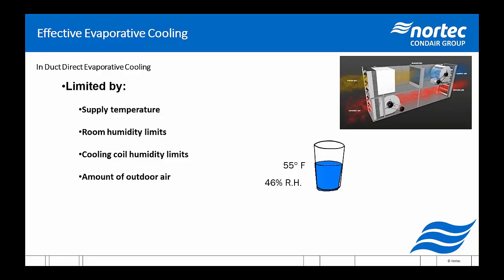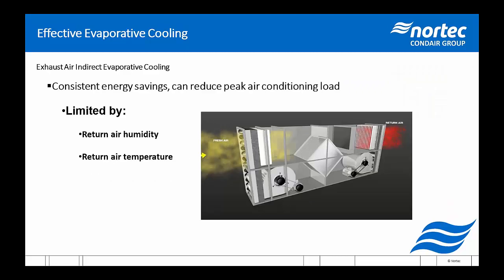If we look at indirect evaporative cooling, this is the exhaust air cooling. So once again, we've got the return air coming from the room, typically 72 degrees and 35% or 74 degrees and 50% in the middle of the summer, but that still allows a fair amount of humidity to be put into the return air to cool it down. We can see a 10 or 15 degree drop before putting it through a heat recovery unit. As a lot of us know, we tend to avoid using heat recovery units in the economizer season because we're just overheating the air. However, during the peak heating season or peak cooling season, we'll see energy savings here from the cooling side.